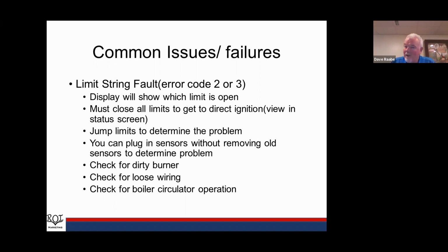And we can actually jump the limits out to determine which ones are the problem. So if I think, oh, my flow switch is the first one, I can go jump that flow switch and just see if that boiler lights. Now, if it lights, chances are, though, it's not a bad flow switch. The flow switch is probably right. I may not be flowing any water. So now I've got to start to research that problem.